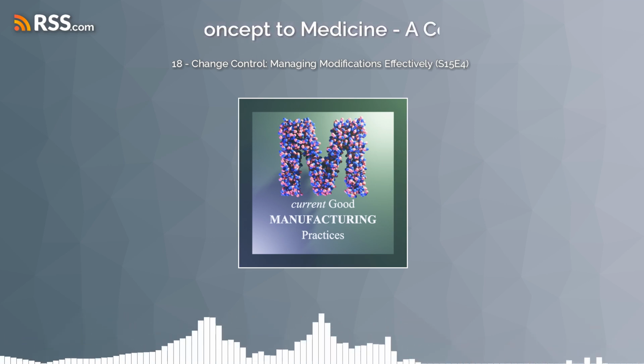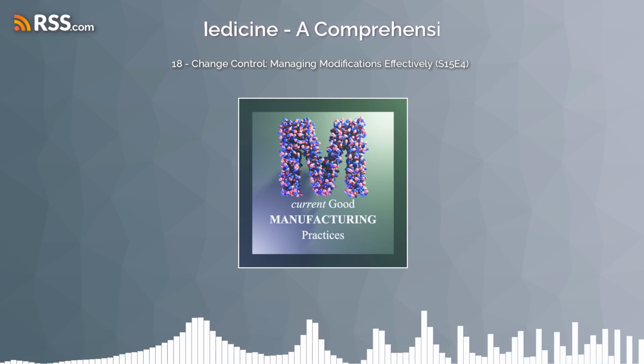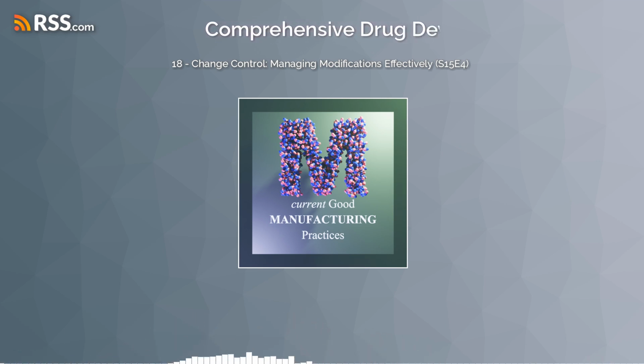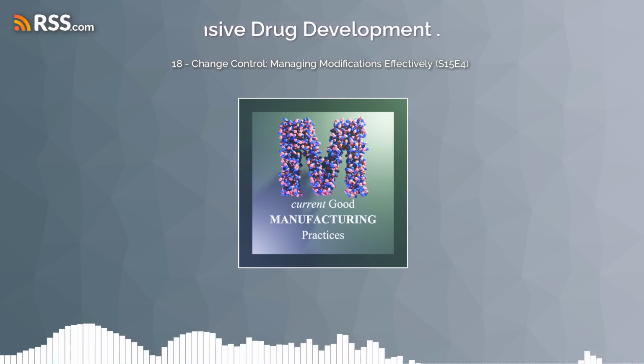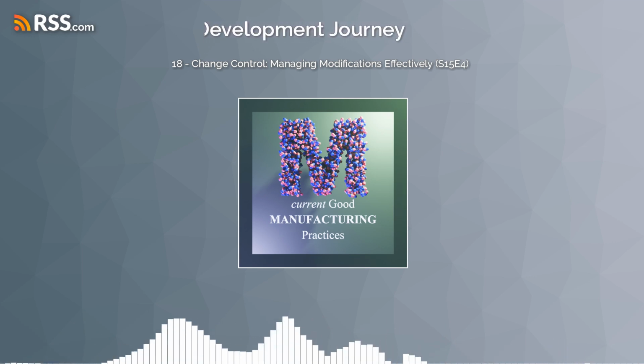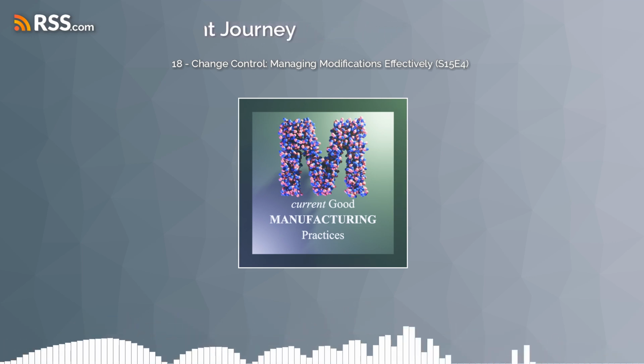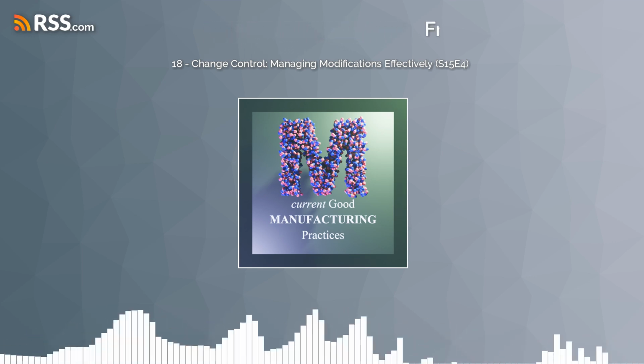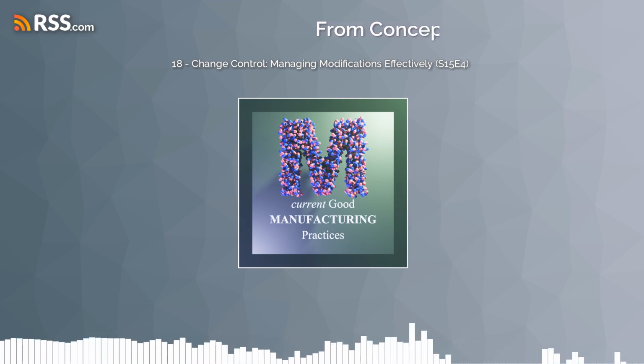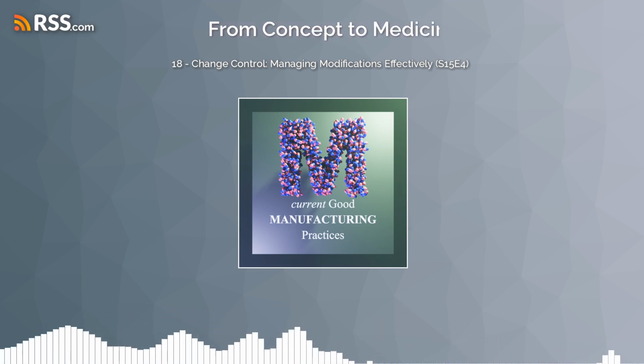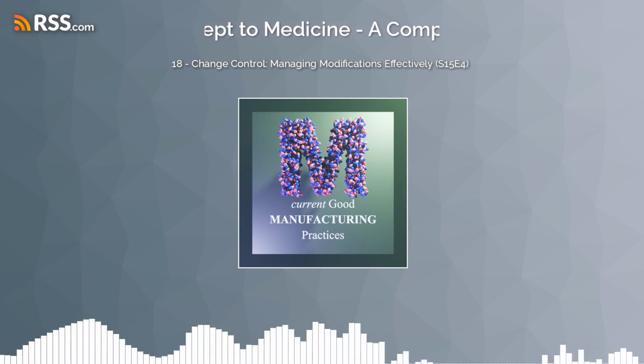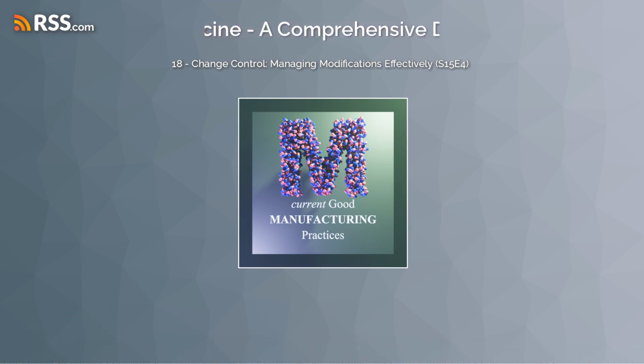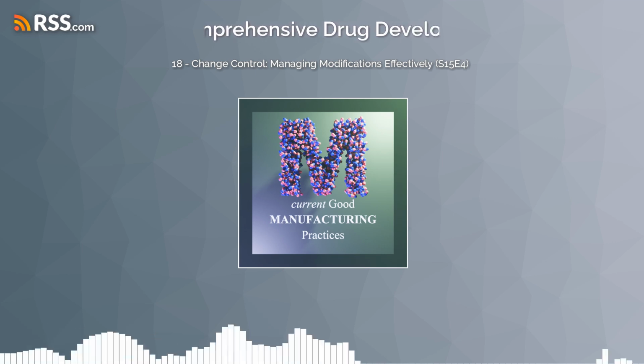Okay, so we've got the evaluation, the approval, and now we make the change: implementation. Right. Implementation, you're putting the change into action. There's a whole plan for it. What's in that plan? A big part is updating those SOPs we talked about. There's actually a checklist in a lab audit guide for good SOPs. They have to be current, clear, easy to find, and you have to review them regularly. So if the change affects an SOP, you have to change the SOP.